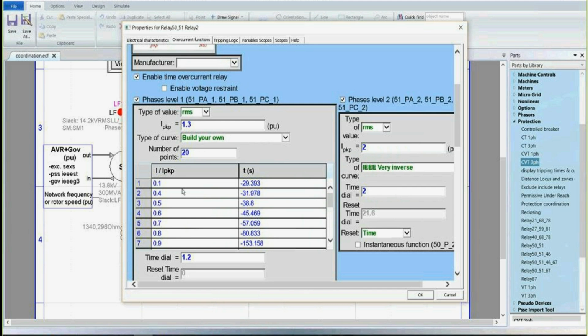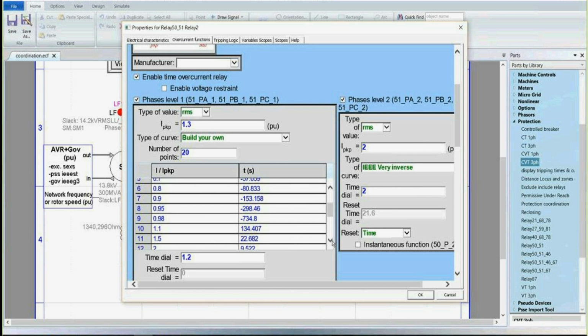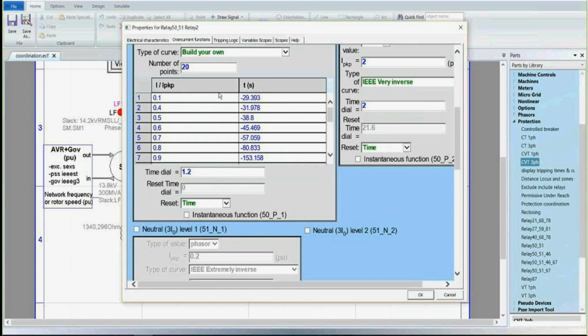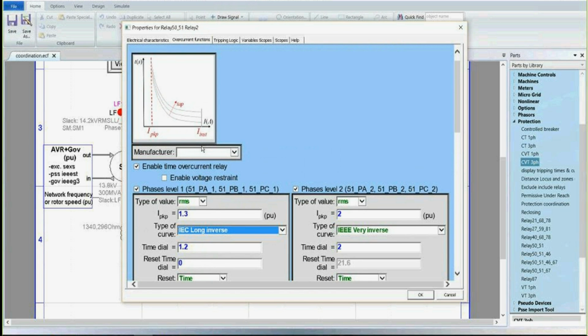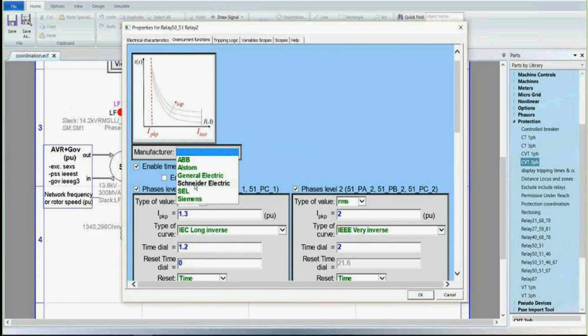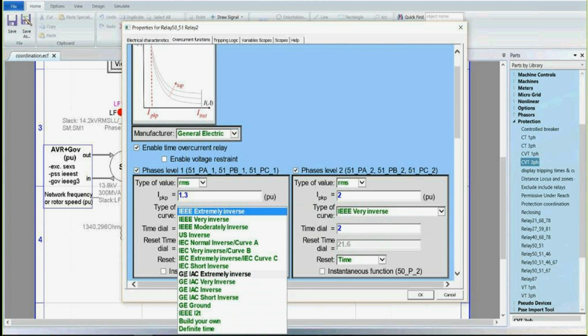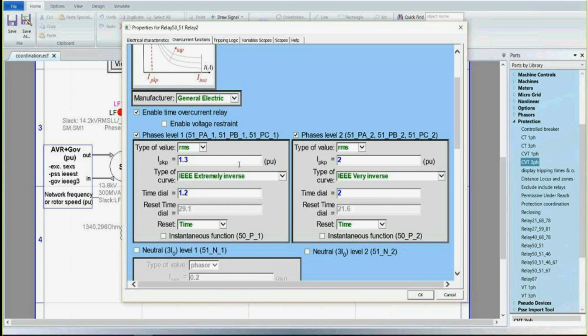So you define the tripping curve point by point. You can put negative values for the reset function as well. And finally, if you select a manufacturer, for example, let's say we select GE, then you will have access to some special General Electric curves, so the IAC.